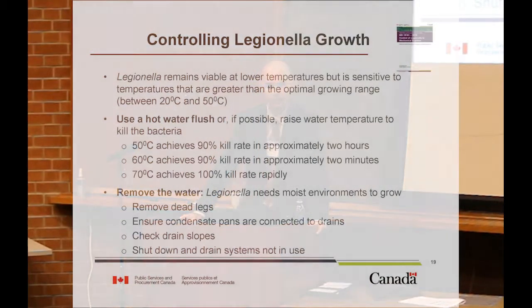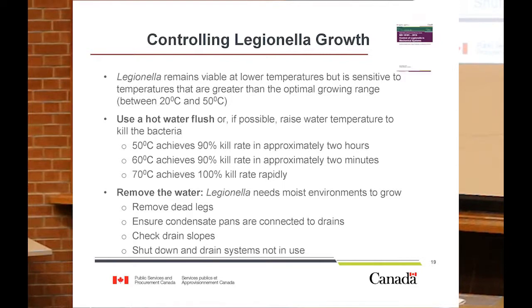Other ways that we look at controlling Legionella growth, again, temperature is a key one, especially when we're talking domestic hot water systems. We want to keep it outside of the growth temperature range. We also use hot water flushes occasionally to remove any potential bacteria in the system. So at 50 degrees Celsius, you're going to get about a 90% kill rate of the bacteria in about 2 hours. That's not very effective. At 60 degrees Celsius, 90% kill rate in about 2 minutes, which is why we want our storage tanks to be set at a minimum of 60 degrees Celsius.